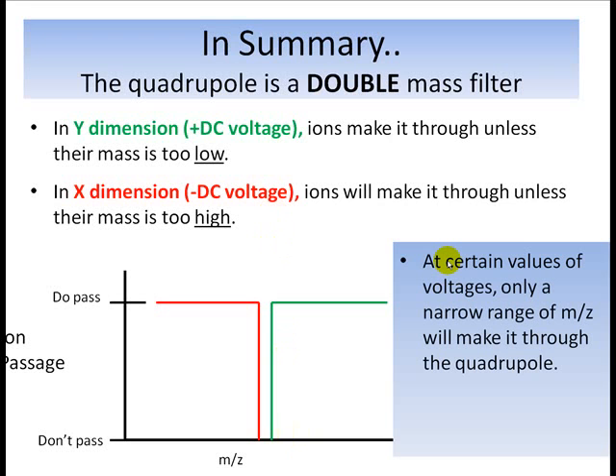So here's how the quadrupole is a double mass filter. At certain values of the DC and alternating RF voltages, only a narrow range of mass charge ratios will make it through. Like this narrow range, this is like a little window that will make it through. If you're below, they will be cut off by this filter. If they're above this window, they'll be cut off by the other filter. And so only a little window makes it through.